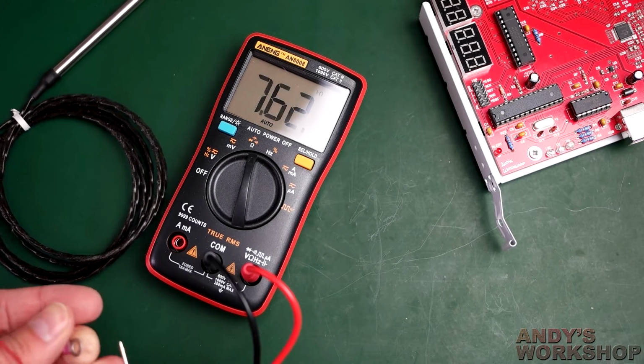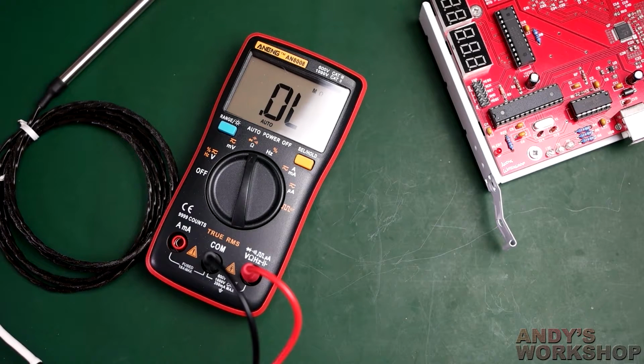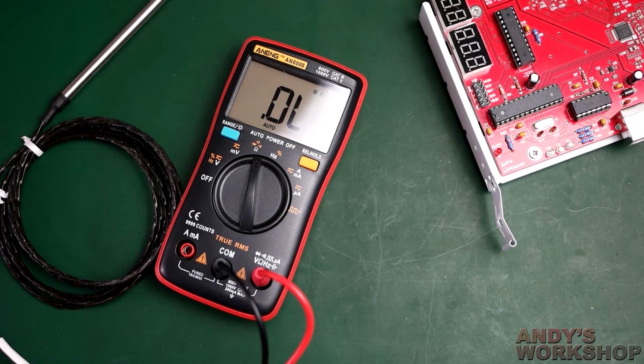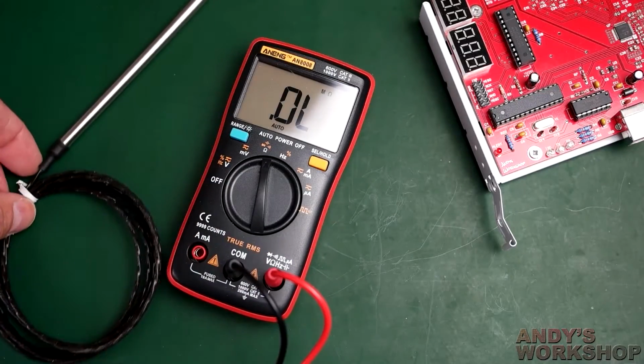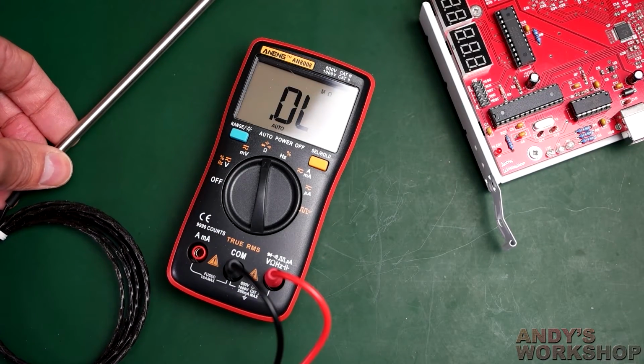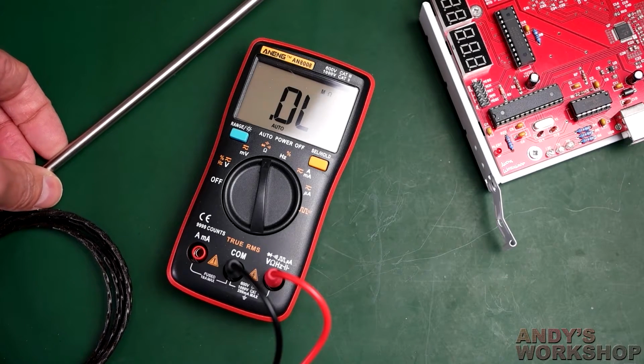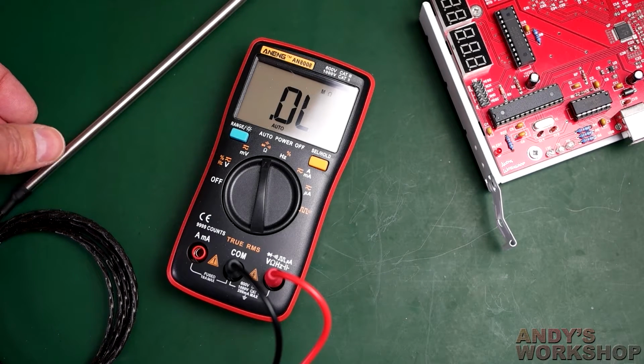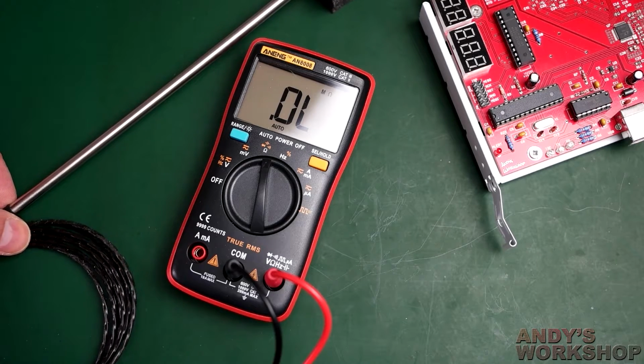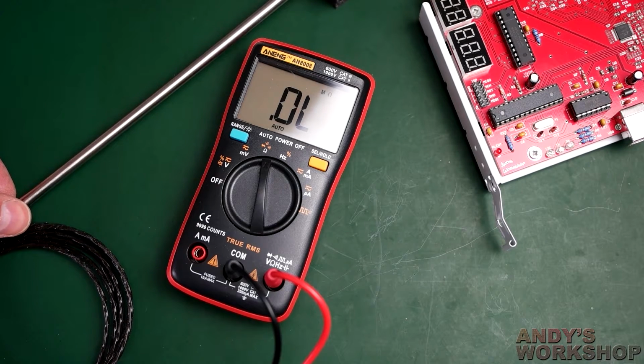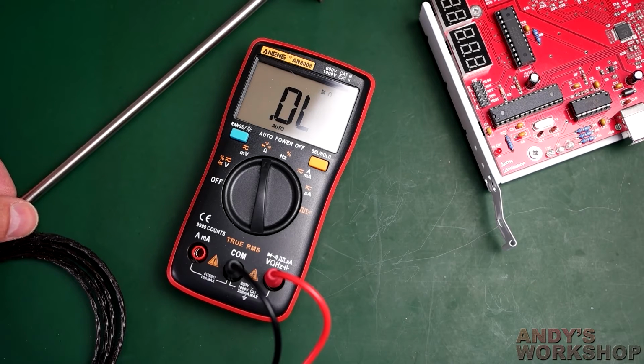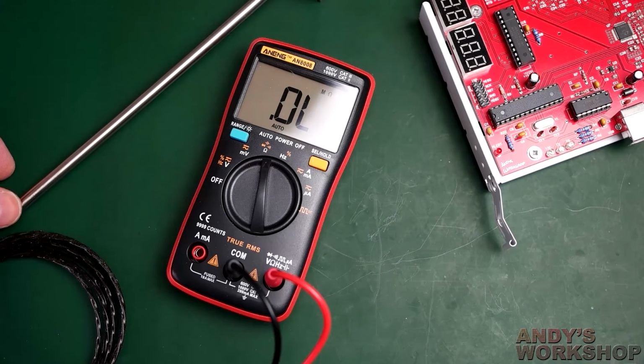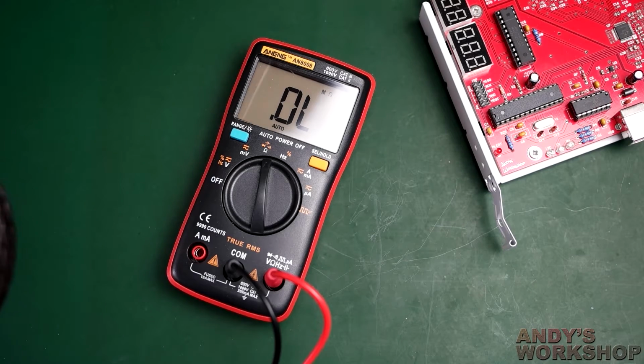So this is the one that I will actually use, and I will use it to calibrate the dodgy ones that I get from eBay. I'll calibrate them, and I'll attach the eBay ones side by side with this good probe, and I'll see how it changes with temperature, just to see if the eBay one does respond with the same linearity as the professional probe. And if it does, then there's no reason why I can't use it. I can dial in the constant calibration value that's required, and knowing that it's going to respond the same way as a professional one. But to start with, I'm going to use the good one.